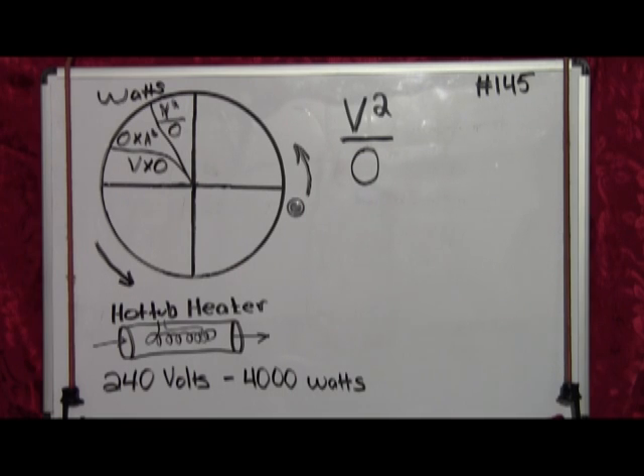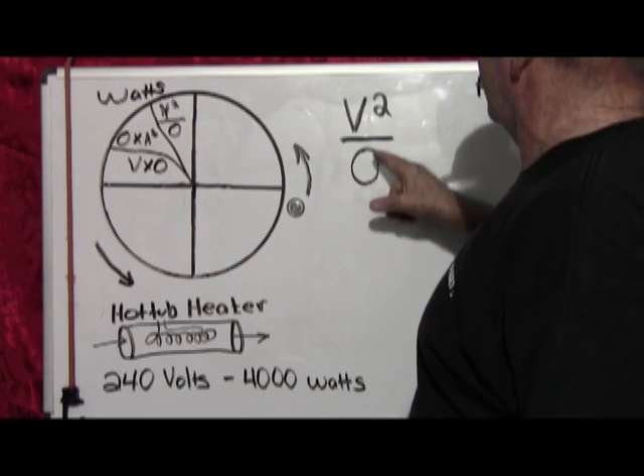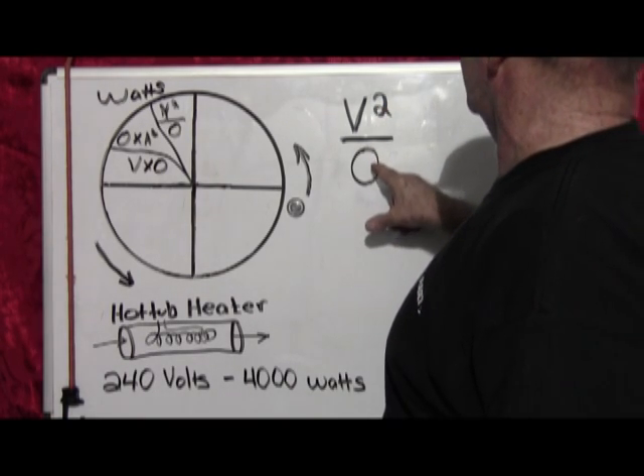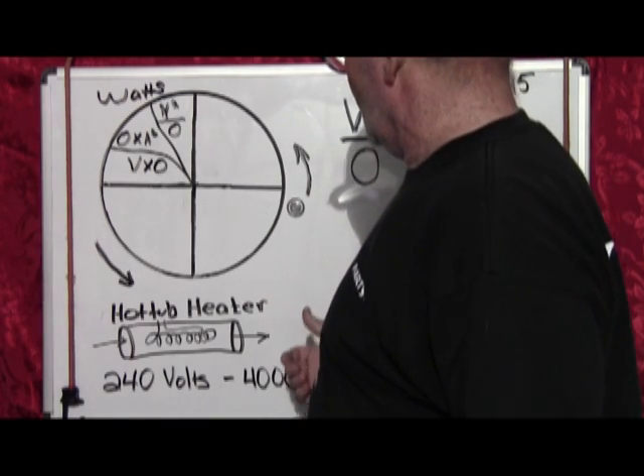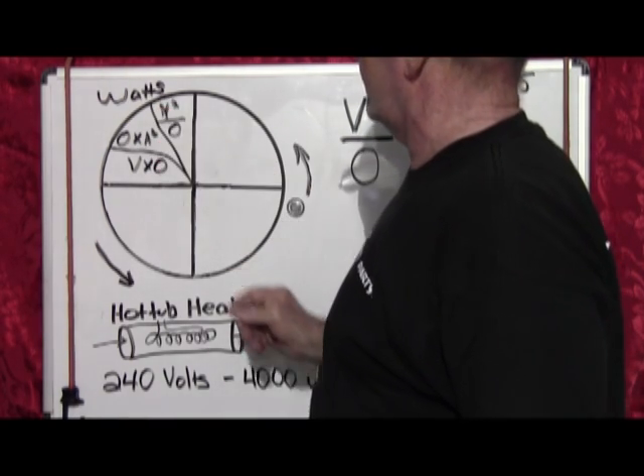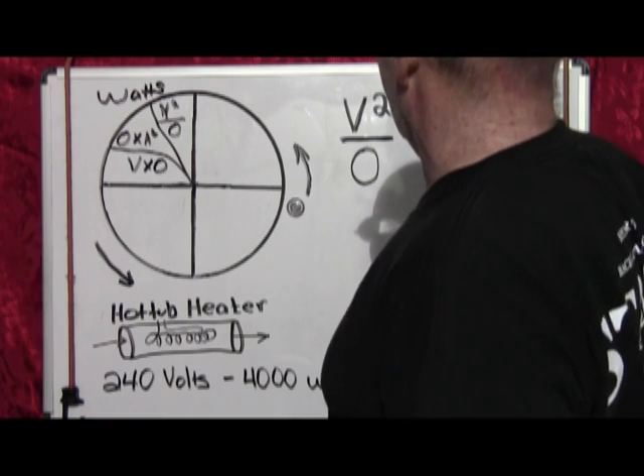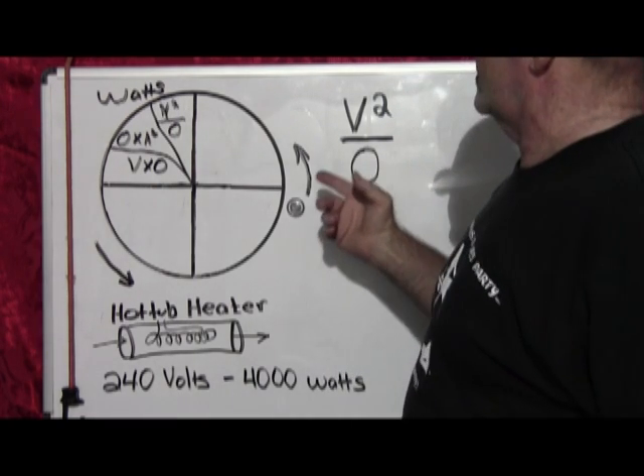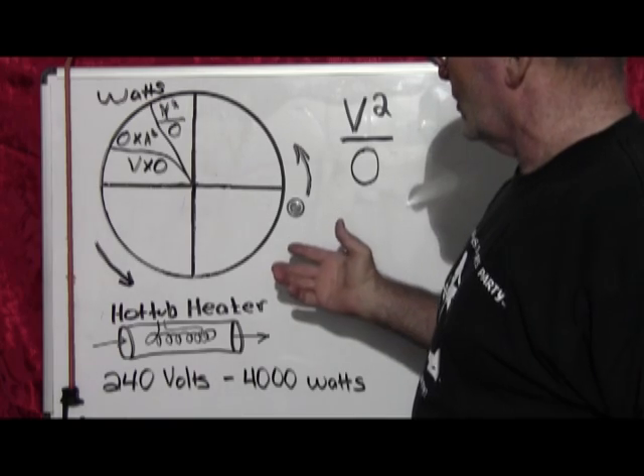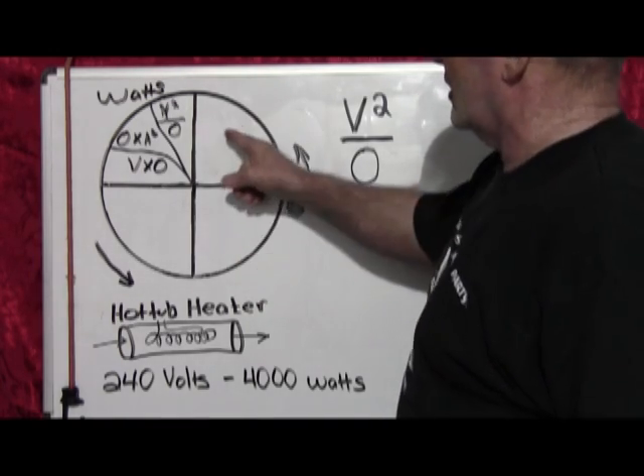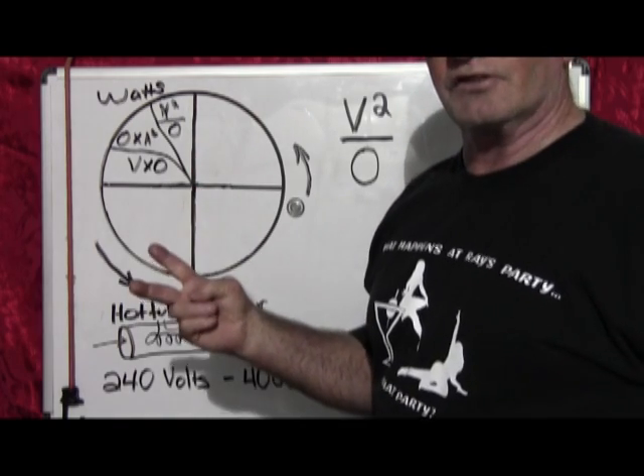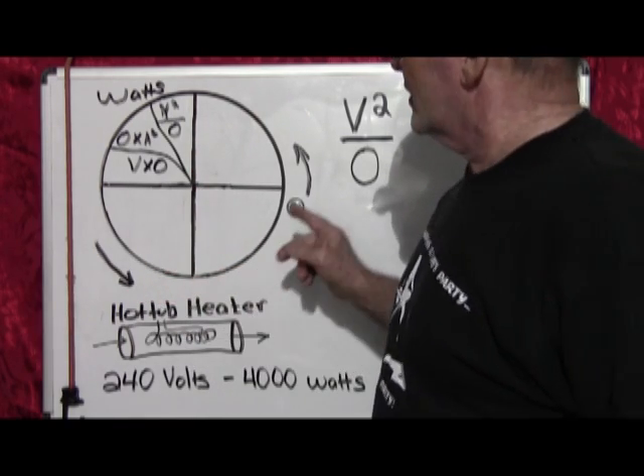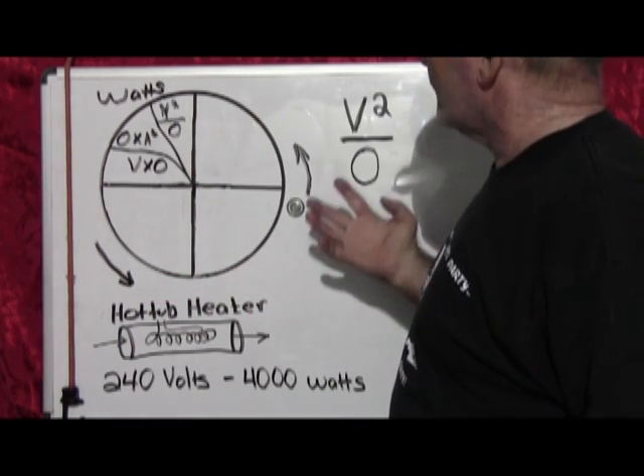The new heaters are 4,000 watts at 240 volts. Now you see here, volts squared over ohms is going to give you watts. That's fine. We know what the voltage is, it's 240 volts, but how do we get ohms? Well, we borrow from another portion of the pie chart.